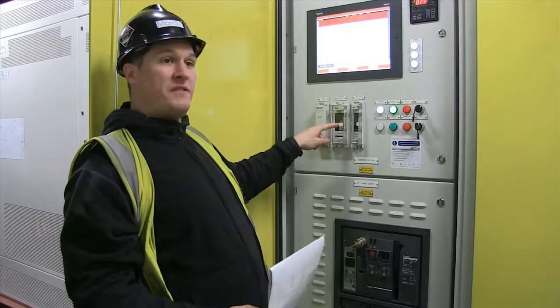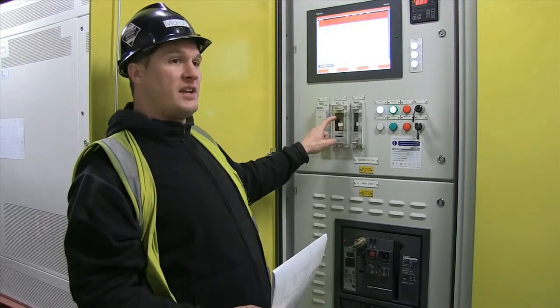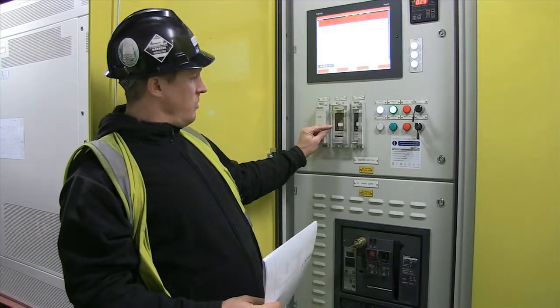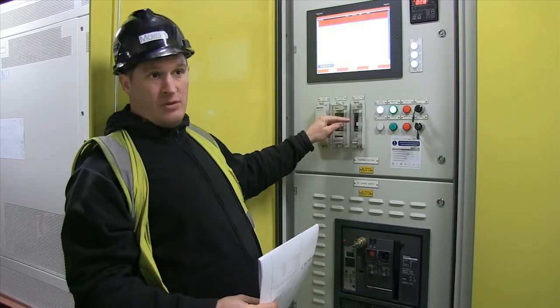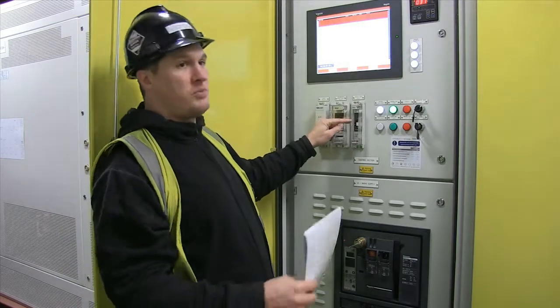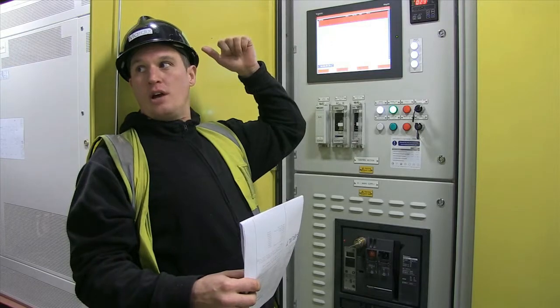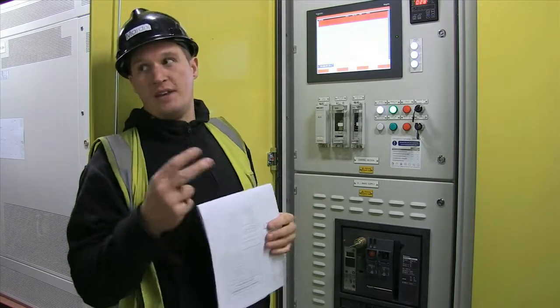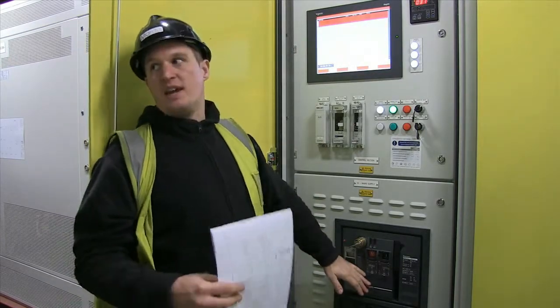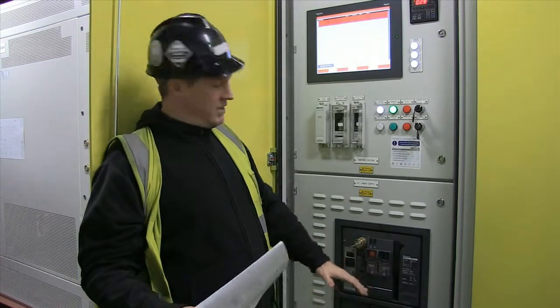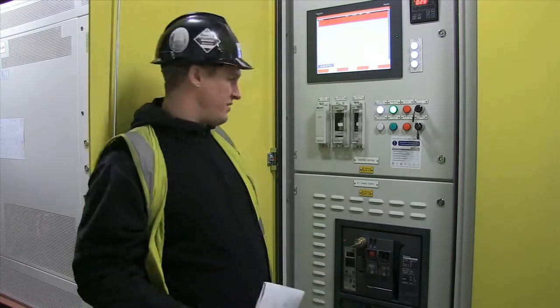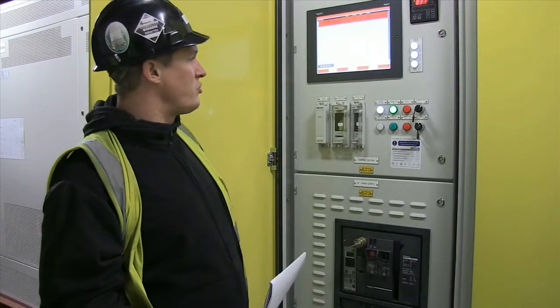So at 250 amp earth leakage, that will drop. When that drops, that will in turn take that out. And then when that drops, that will take out your ring main unit, which will then in turn take out this, and that's your inter-tripping signal right there. You've done that, yeah. Okay. Yeah, I've done that one. Yeah. So you know all about the inter-tripping.